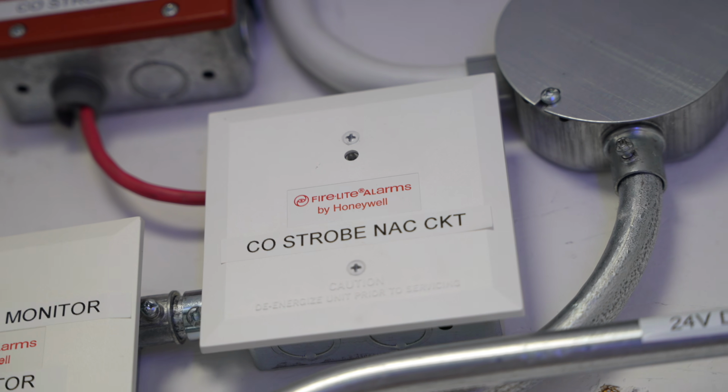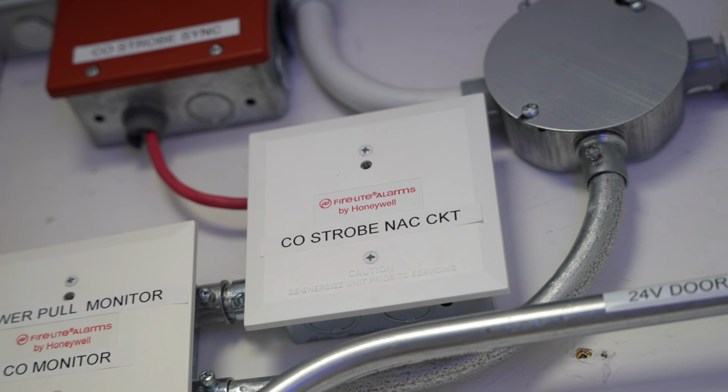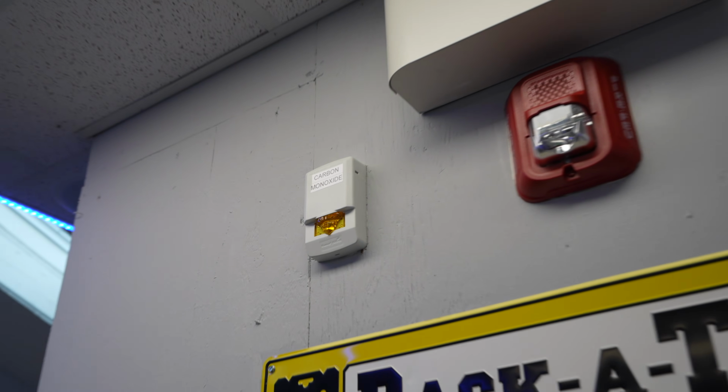Why it was like that, I don't know, because I was able to zone a NAC in the house system on the Notifier NFS 320 to a supervisory. It just does its own thing, nothing to do with the other NACs. That worked fine. Why this system was causing me problems, I don't know. But long story short, that guy is basically the NAC for our carbon monoxide strobes.